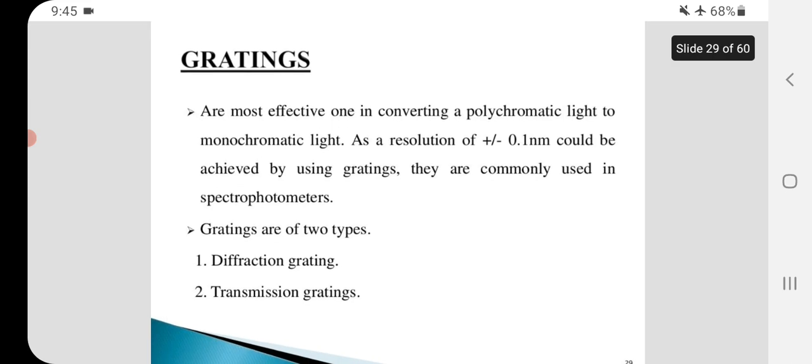Gratings are the most effective in converting polychromatic light to monochromatic light as a resolution of plus or minus 0.1 nanometer could be achieved by using gratings. They are commonly used in spectrophotometers.